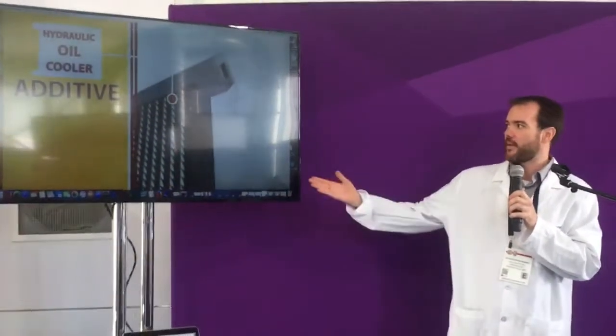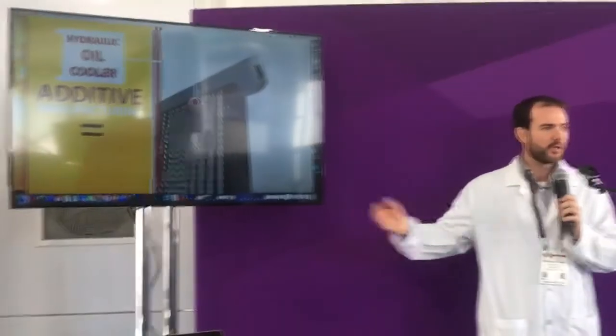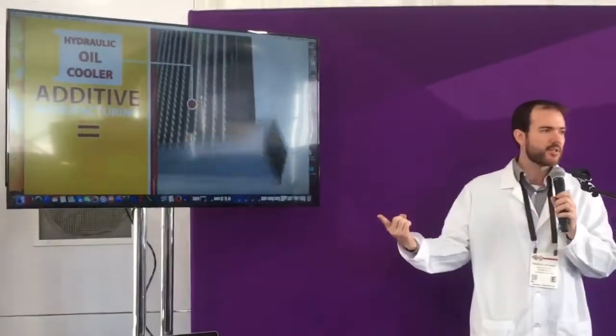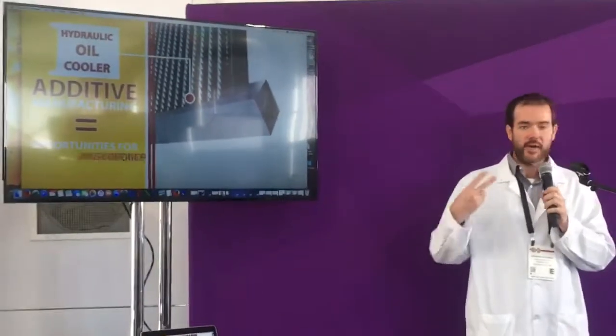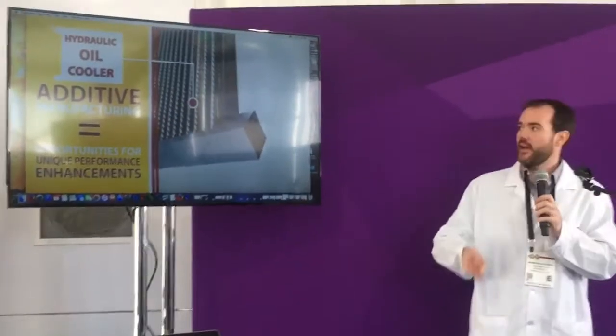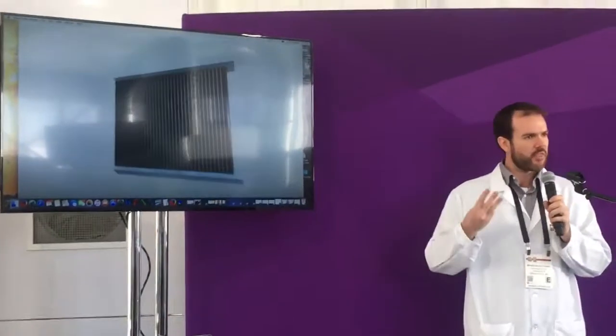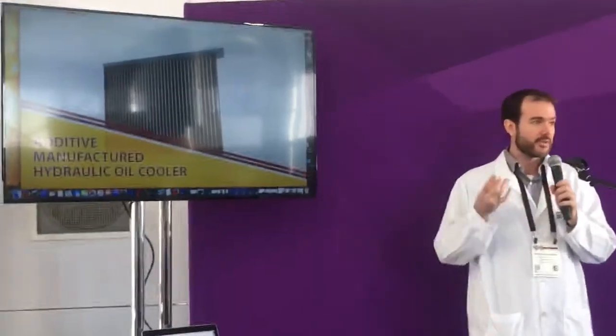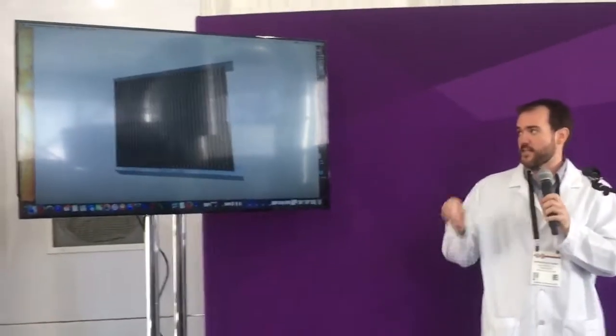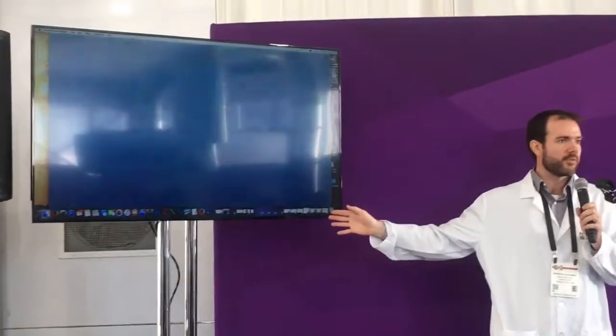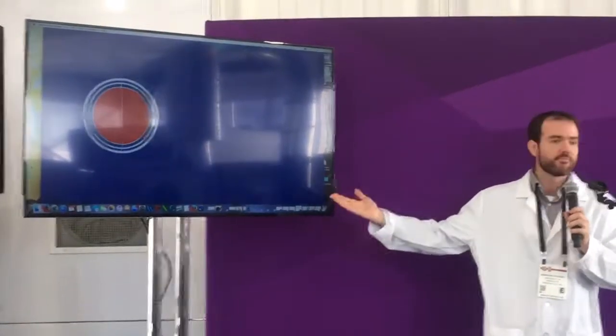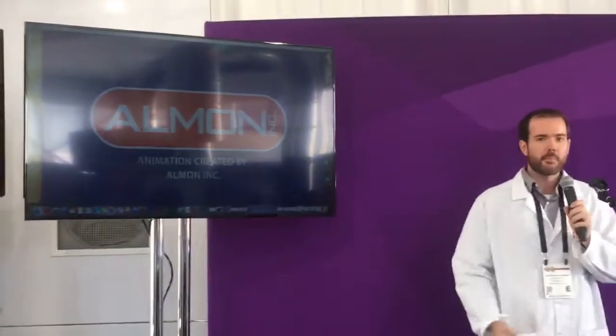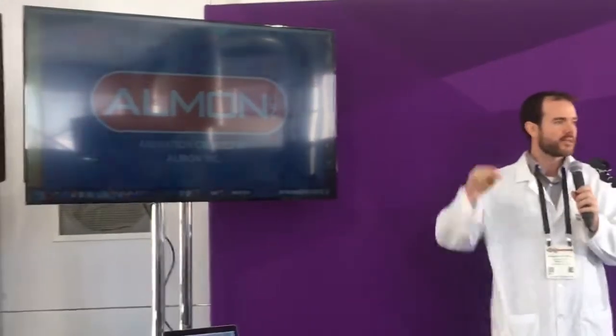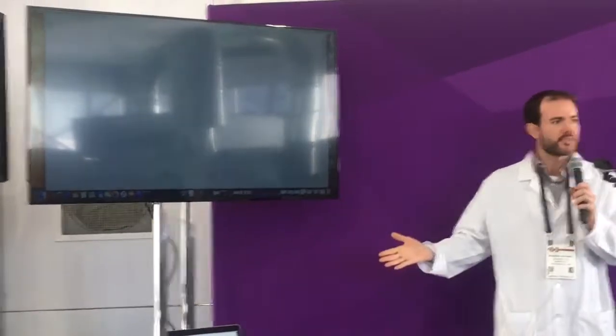Alright, so you can see those features together is sort of the big thing. We're able to include external fins for maximized surface area, external shaped tubes for aerodynamics of the flow to reduce pressure drop, and internal offset strip fins to break up those thick viscous boundary layers that you have with oils in order to get maximum heat transfer. Including all of those different features in a single device is something that's uniquely possible through 3D printing processes. Additive manufacturing has brought us a great device that is a drop-in replacement, completed in a single printing operation, that only requires the hydraulic fittings be added and some mounting points created. So that covers our process.